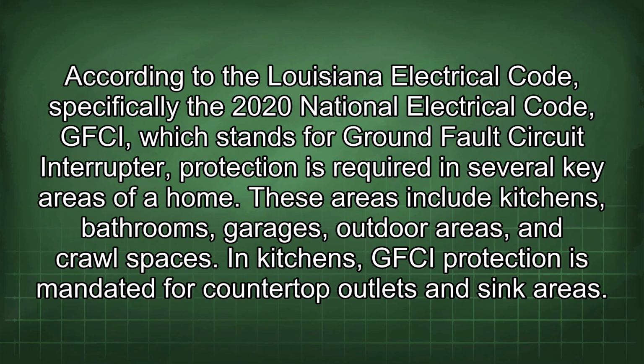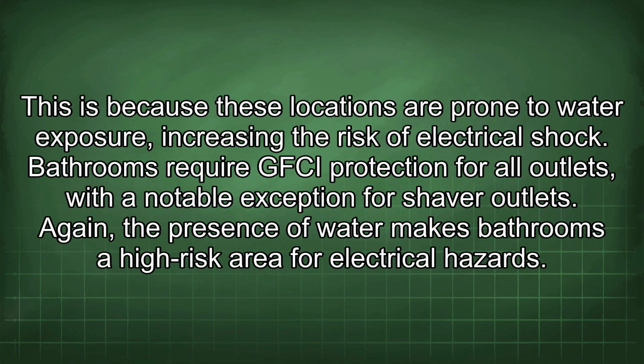According to the Louisiana Electrical Code, specifically the 2020 National Electrical Code, GFCI, which stands for Ground Fault Circuit Interrupter, protection is required in several key areas of a home. These areas include kitchens, bathrooms, garages, outdoor areas, and crawl spaces. In kitchens, GFCI protection is mandated for countertop outlets and sink areas. This is because these locations are prone to water exposure, increasing the risk of electrical shock.